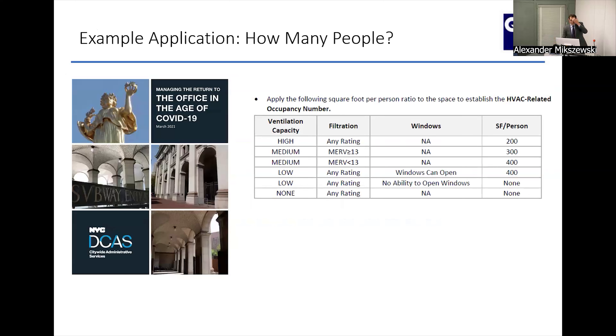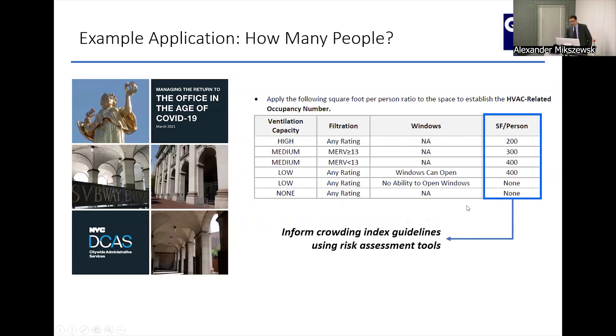How did organisations use the tool? I was working with New York City public buildings, and the tool was a factor in the reoccupancy. The ventilation capacity of the space was used as an adjustment to square footage per person. A fundamental decision was made that buildings with no mechanical ventilation were not going to be reoccupied. Where windows were operable, it was very low density, and filtration and ventilation were considered in the reopening guideline — which was a major step forward.